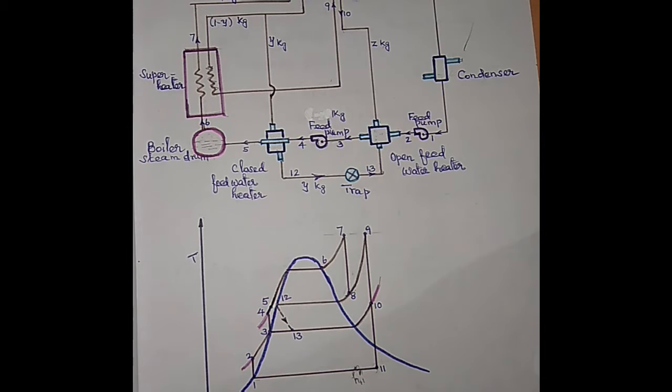Okay. So the advantages I will repeat again. By reheating it, work done increases, thermal efficiency increases, erosion of the blade decreases, because the dryness fraction increases. Wet steam causes more erosion, and wet steam causes more internal losses.